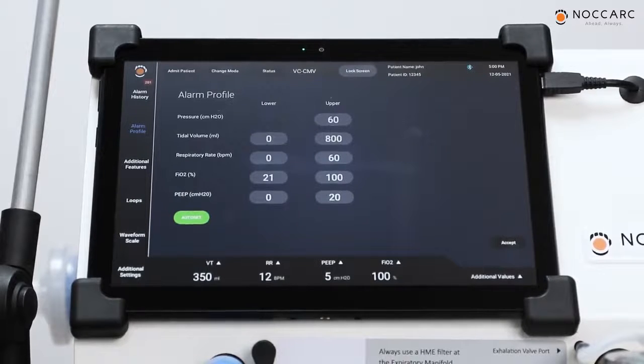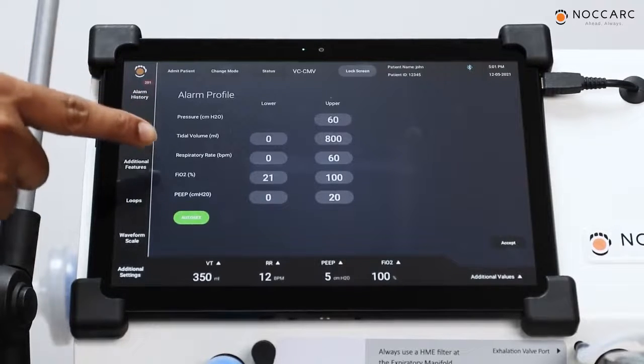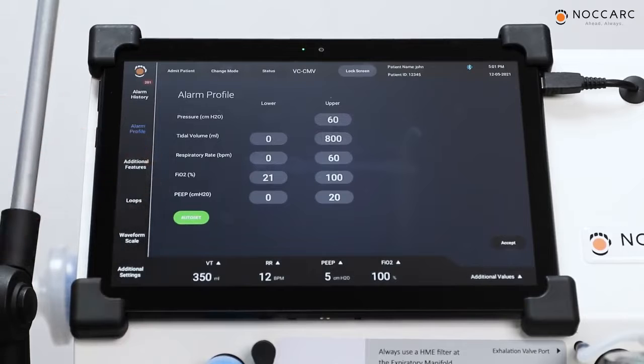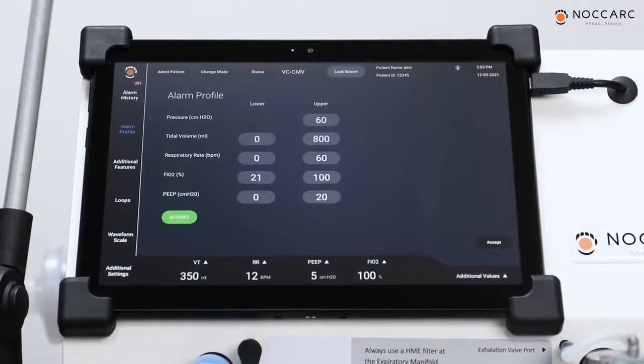The next window will be your alarm profile. Here you can set the lower limits and upper limits for the particular parameters, including pressure, tidal volume, respiratory rate, FiO2 and PEEP. According to the set parameters, you have to set the lower limit and upper limit for those particular parameters. When we accept the set ventilation mode window, the next window will be the alarm profile. The user has to compulsorily set the alarm profile while selecting or switching to a new ventilation mode. This is for safety reasons.